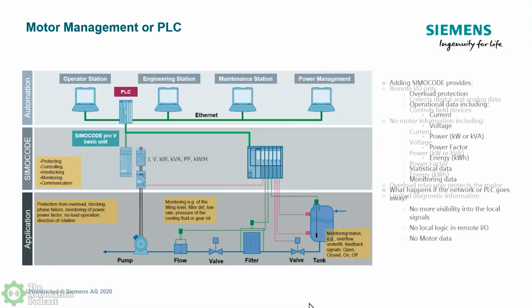Now, if I introduce the SIMOCODE, what can it give us? Well, we're using the same communication protocol as the IO, but now when I introduce the SIMOCODE and put in the CT and make it my overload, and I'm using a PT, a current transducer and a power transducer, now I can give you current draw, voltage, phase imbalance, phase loss, kilowatt hours, kVA, power factor. I'm not controlling it, but I'm reporting it back to you to let you know what's going on. And then I can give you statistical data: how many times the pump turned on, how many times it turned off, how long it was down for.